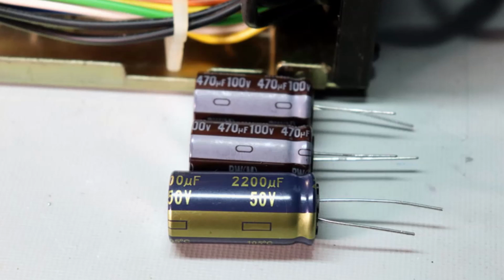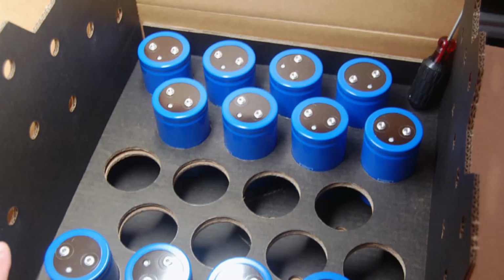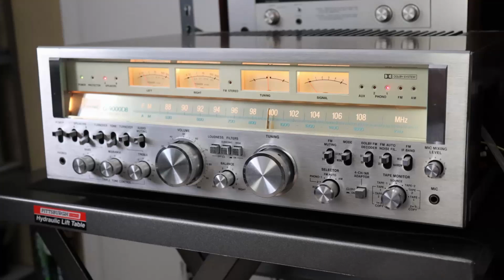But just a few pennies more, these data sheets on these manufacturers' websites, if you want to know the difference, they'll say if you lower it 10 degrees Celsius, this is what happens to the reliability of that capacitor. If you run this capacitor 20% under voltage it's rated, here's what you can expect. But if you look at all the parameters, all of the manufacturers, basically what they're going to tell you is you're probably going to get 15 to 20 years out of these capacitors and have them still meet their original specs. You can probably see I'm kind of in the camp of changing out old electrolytic capacitors.